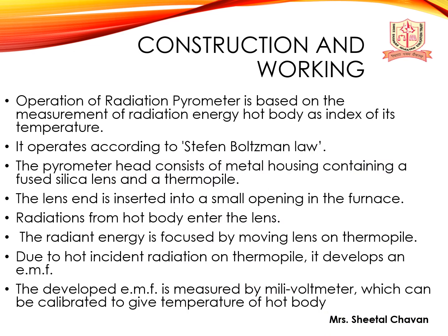Construction and working. The operation of the radiation pyrometer is based on the measurement of radiation energy from a hot body as an index of its temperature. It operates according to the Stefan-Boltzmann law. The pyrometer head consists of a metal housing containing a fused silica lens and a thermopile. The lens end is inserted into a small opening in the furnace.